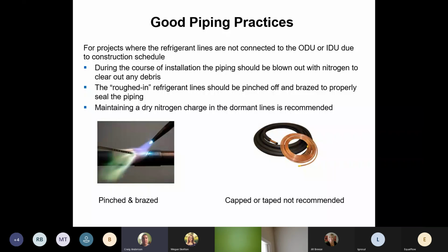So start crimping the lines outside. I'm not saying braze them, but at least by crimping them, we're taking that part of the equation out so our lines are clean when we go back. With all this modulating stuff, we don't want anything floating around in there. It could just cause havoc for the service guy that's going back.